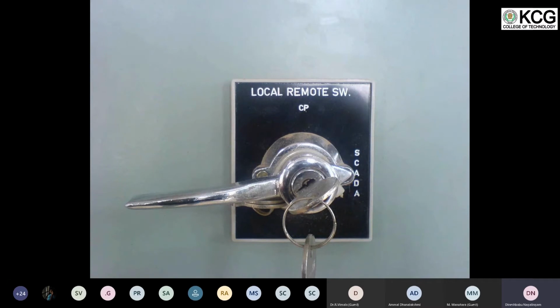So this is the interlock. And to ensure that, when it is in SCADA position, some operator should not come and immediately put it in CP and start its operation, there is a key. They will lock it and put it in a board. And when you want to take the key, you have to get permission from the SCADA system engineer. So this is how the local remote switch works.